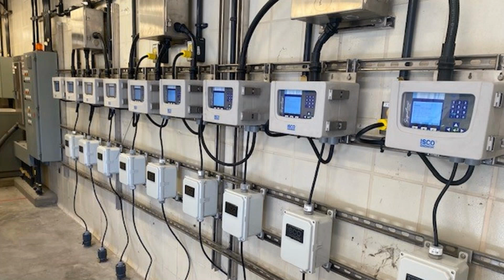There's an example of where we have 9 of our signature meters installed, all with IS barriers and enclosures. And what they had done here is they'd sealed off each one of these conduits. That way no hazardous gases could reach into this safe area.